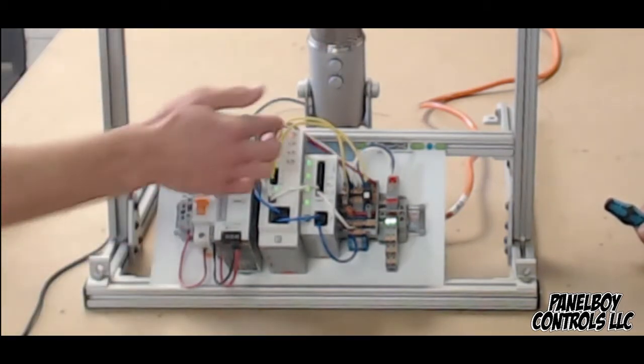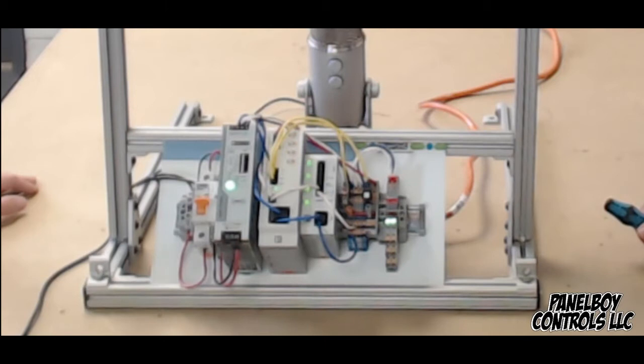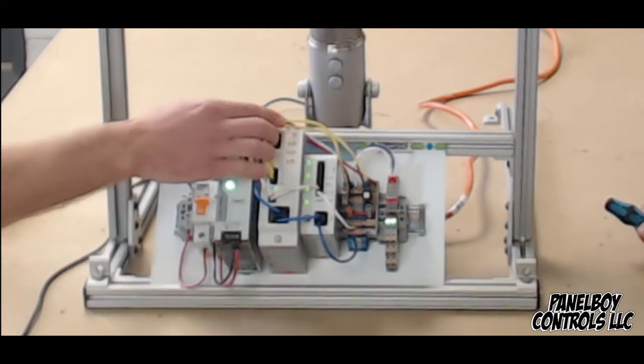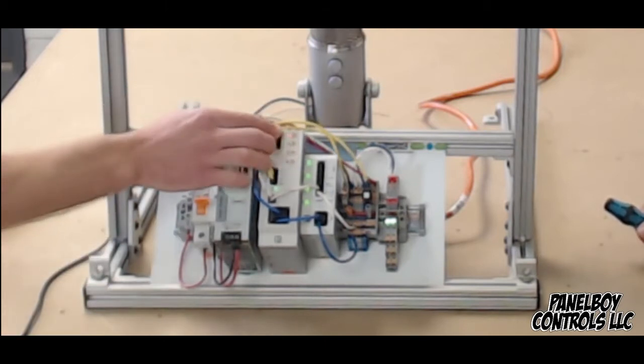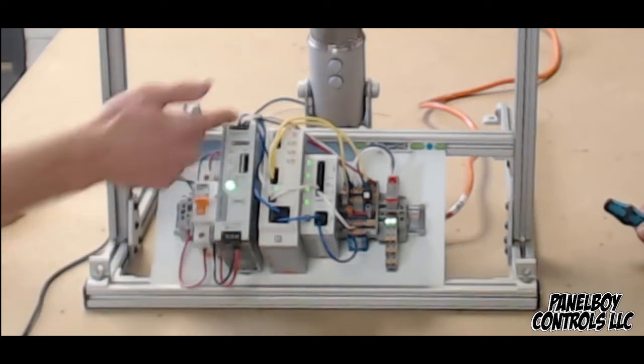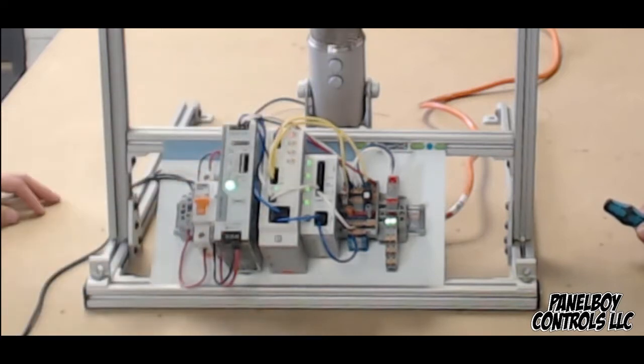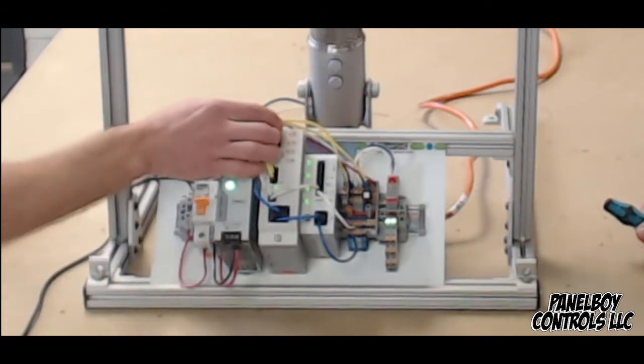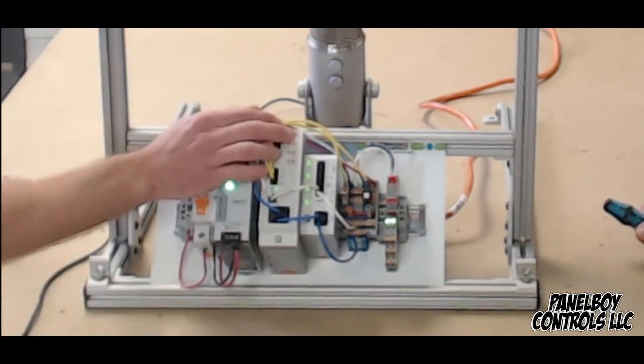That light's going to go out if any one of these 4 channels has been tripped. Likewise, you'll see on the circuit breaker module itself, so I open up the panel, I see that circuit number 1 is tripped. There's easy indication right there that, okay, that's where my problem is. I can diagnose that circuit, see where the short circuit is or where the overload might be coming from. I can reset it by pressing this button.